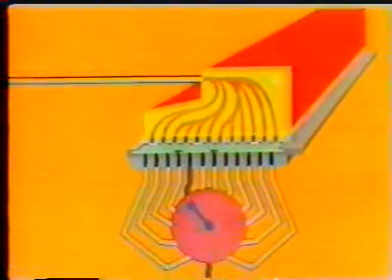A distribution plate is provided for each output. The plate has a channel leading to the output for each step. In distribution plate C, for example, an output signal is issued in the second, fourth, and 11th steps. Since the signals are issued in a low pressure range, they must be amplified. The program is limited by the size of the card.